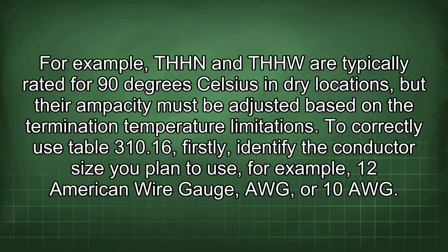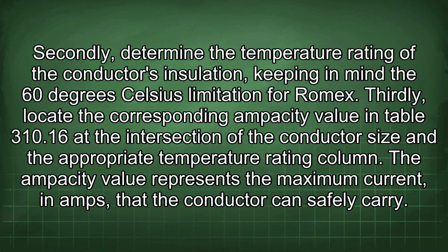To correctly use table 310.16, firstly, identify the conductor size you plan to use, for example, 12 American wire gauge, AWG, or 10 AWG. Secondly, determine the temperature rating of the conductor's insulation, keeping in mind the 60 degrees Celsius limitation for Romex. Thirdly, locate the corresponding ampacity value in table 310.16 at the intersection of the conductor size and the appropriate temperature rating column. The ampacity value represents the maximum current in amps that the conductor can safely carry.